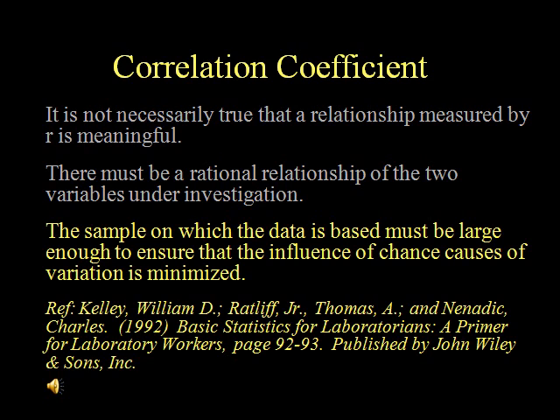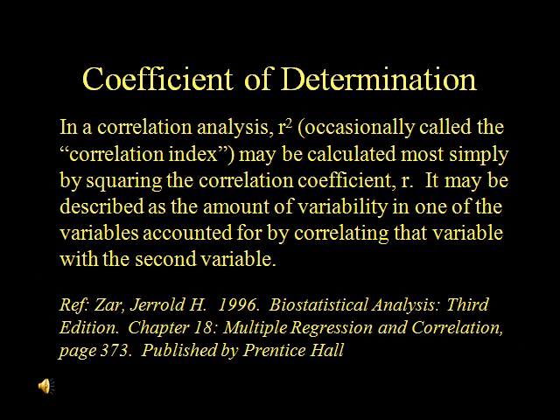In addition, the correlation coefficient must be made up of a large enough sample size to minimize the causes of variation. Along with this, a correlation coefficient would not be useful when using only 2 standards for a linear or 3 standards for a quadratic. In these cases, the correlation coefficient would be equal to 1.00.